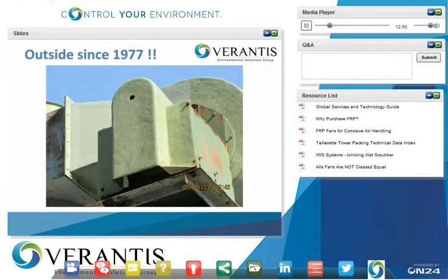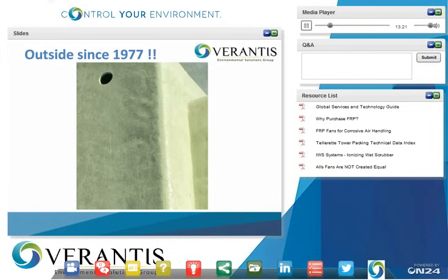This is a picture of one of our dust collector fans that's been in service since 1977. This fan's only probably been taken out of service 2 times in the last 37, 38 years and been rebuilt. Also, if you look right here, you can see a white line. That white line is actually where the top coat over time has weathered and worn away, and its glass fibers are starting to show. Here's a close-up of that same photo. You can see the glass fibers that are exposed.